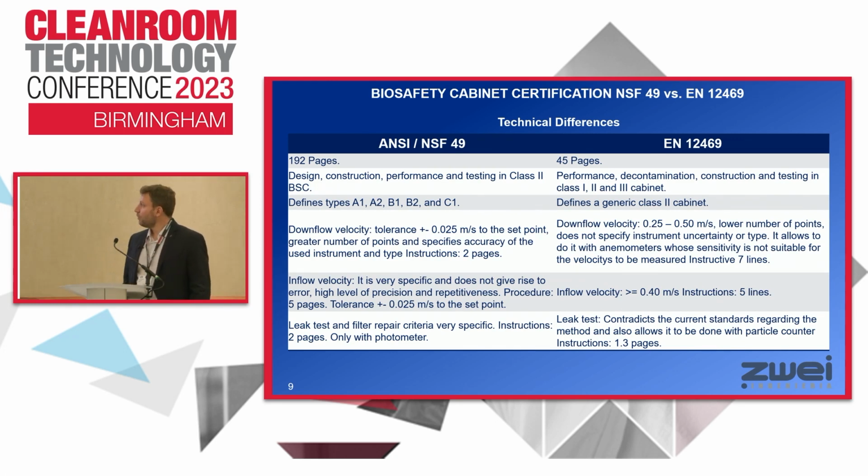Regarding the inflow velocity, the test is very specific in NSF, having a 5-page procedure, very specific about what to do, and that gives us a high level of precision and repeatability.